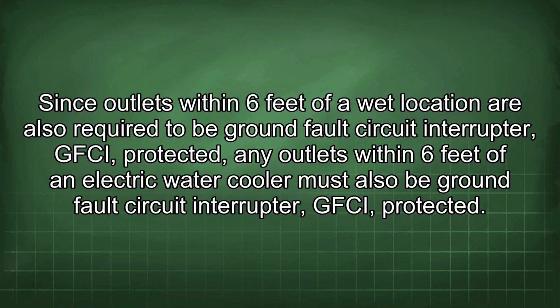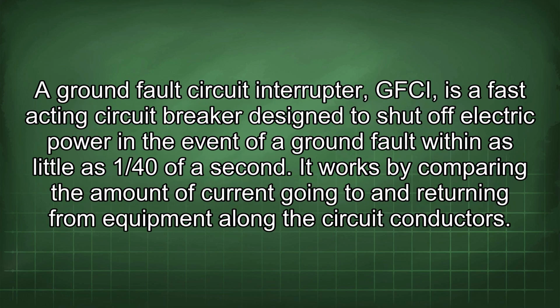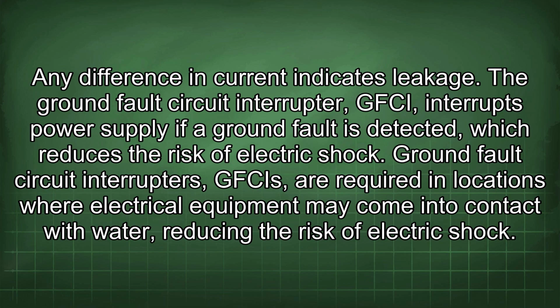A GFCI is a fast-acting circuit breaker designed to shut off electric power in the event of a ground fault within as little as 1/40 of a second. It works by comparing the amount of current going to and returning from equipment along the circuit conductors. Any difference in current indicates leakage. The GFCI interrupts the power supply if a ground fault is detected, which reduces the risk of electric shock. GFCIs are required in locations where electrical equipment may come into contact with water, reducing the risk of electric shock.